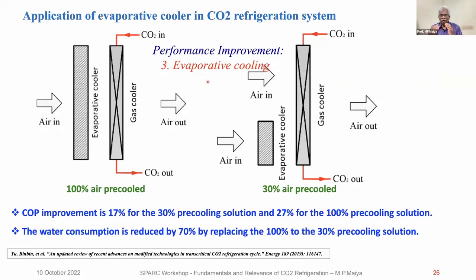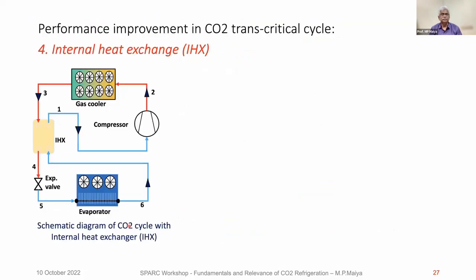You can use evaporative cooling. All of us know the evaporative cooler, but whether to use it full or half or one third, because this is a very high temperature, already 90 degrees centigrade. What is the use of cooling air from say 40 to 30? Not much effect. But at the fag end of the gas cooler, you will get benefit. You can see here the COP improvement is 17% for 30% pre-cooling, whereas 27% for 100%. Of course, you'll get better, but at the expense of a lot of water. Water consumption is much higher. You have to optimize that also.